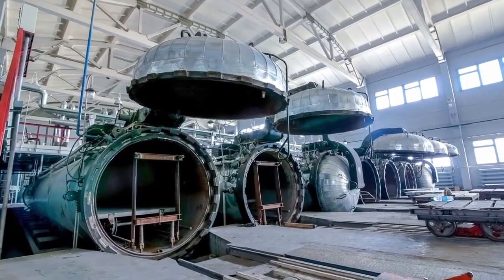A brazed plate heat exchanger is essentially a set of printed stainless steel plates. There is a print on each, and it always uses a copper sheet, or a nickel one. The heat exchanger is assembled by placing the plates one on top of the other, interposing the copper or nickel sheets, and positioning the nozzles. Once the heat exchanger is formed, it is placed in a vacuum oven at the melting temperature of copper or nickel.